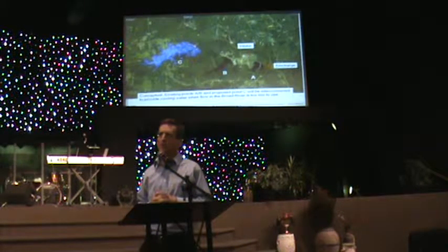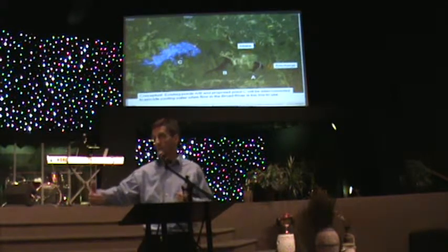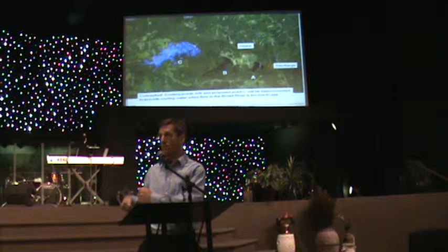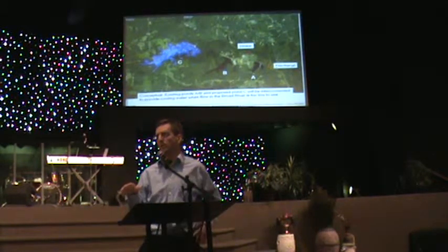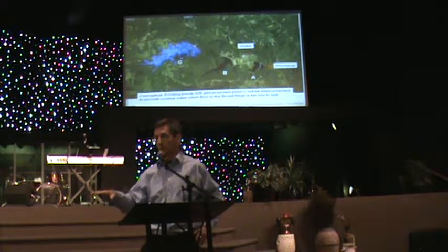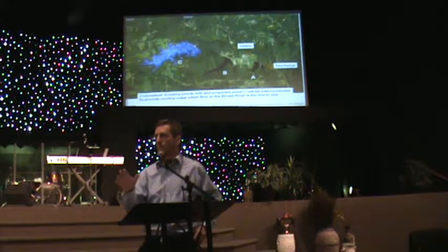In the winter, the main issue that we would be looking at is the water quality criterion that says there can be no greater than a 5-degree increase in a stream. So with a 44-degree river temperature, that would be the primary issue. The other water quality criterion that we look at is a 90-degree Fahrenheit, just flat-out temperature for streams. That's another water quality criterion, and that would be the limiting criterion in the summer. So they used an 88 river temperature in the summer, and that's what was modeled.